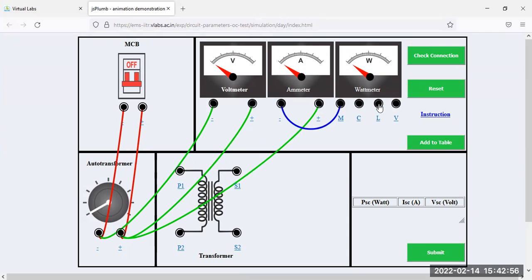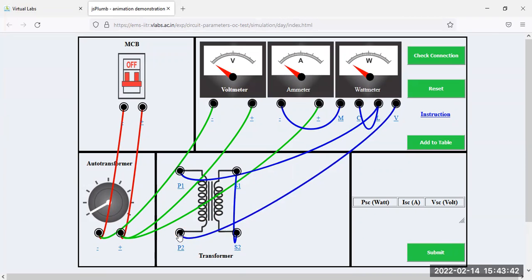And as you know that L and C are common, so just short this L and C, and this L goes to the HV side. Okay, so P1, this one is positive and this one is the negative polarity of this HV winding. Okay, and this one is positive and this one is negative of this LV winding. So just short this one. Yeah. And next, from this V polarity terminal of the wattmeter, connect to the negative polarity of this HV winding.